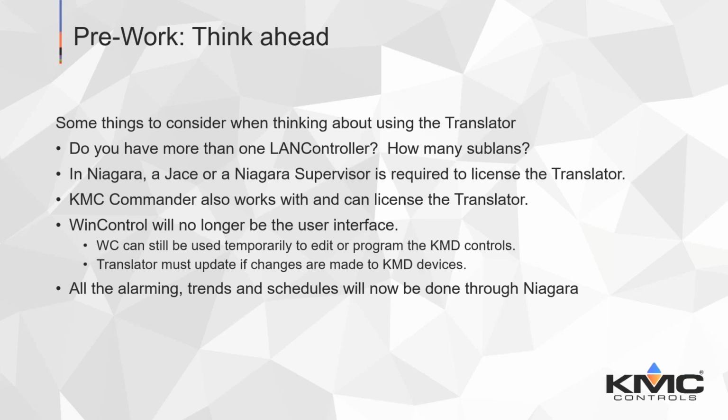All that's going to have to be recreated in your Niagara front end. Alarming currently in KMD is done in Control Basic. Those alarms go out on the network, and if there's nobody to receive them, they get clogged up on the network. You should take those out. So you're going to have to go in and edit all the code on all the alarms. You should, yes. That's a little pre-work tip for you. But the payoff would be faster token times and better resulting bandwidth to get data into Niagara. Yes, correct. Okay, cool.